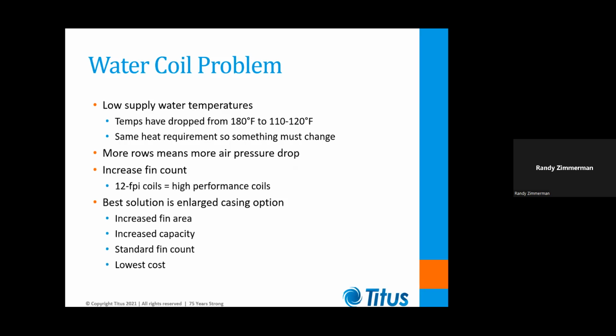Now, another thing we run into: most of the coils in this industry were designed for an entering water temperature of 180 degrees because that was the standard for so long. But now people are using the newer condensing boilers, which tend to run most efficiently somewhere between 110 and 120 degrees. And of course, we have the same heating requirements we've ever had. So if we want to deliver the same heat, but we've got lower entering water temperatures, something's got to change.